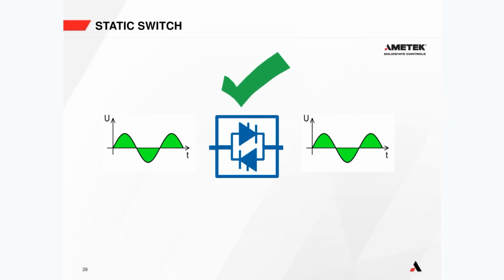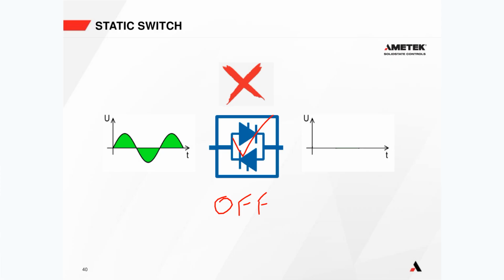And then if we add them both together, we connect them in inverse parallel or reverse parallel. Then the top SCR allows the top half of the waveform to get through, and the bottom SCR allows the bottom half of the waveform to get through. So if we send a signal to this static switch, then the whole of the waveform from the input will get to the output. The switch is on. Remember, it's got no moving parts. It's done by semiconductors. But if we remove the signals from these SCRs, the switch is off, and therefore no AC will get through the switch.